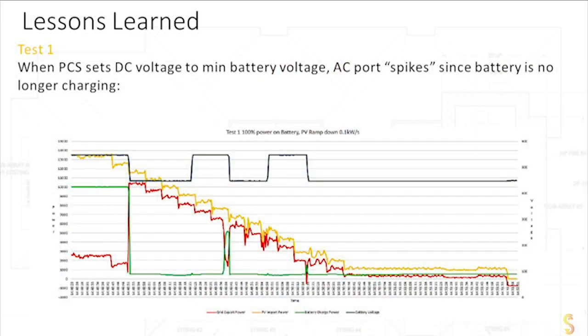Here are some examples of this test actually being performed. What you see on the screen in front of you is a battery at a certain voltage in the dark line labeled DC voltage. So on the far left, you see a constant battery voltage. This is the voltage that the battery operates at. The yellow or gold line is the PV power, so the sun is up and the power is up, and that's why you see the yellow line or the gold line up high. The sun is up, the power's flowing. And then of course you see the battery is charging, the green line, which it can do because it's operating at its voltage window. And the red line is the utility power.